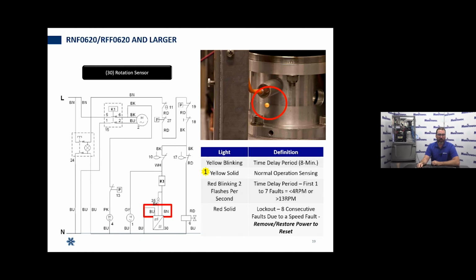We are in a shutdown at this point. The machine is just idling, sitting there neutral. So in order to clear that out of that RPM sensor, you would need to remove and restore power to that machine to get that to clear. And of course, you'll go back into the initial time delay of 8 minutes, yellow blinking. If in fact we have RPM at that point in time, you'll see that light go solid.